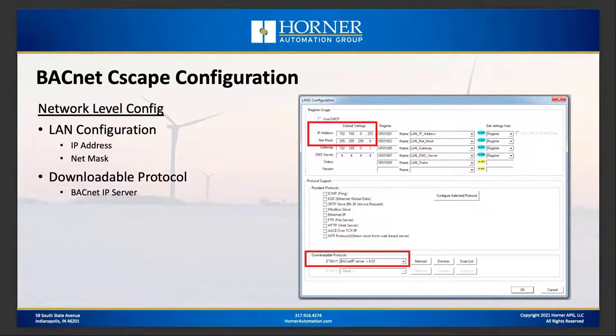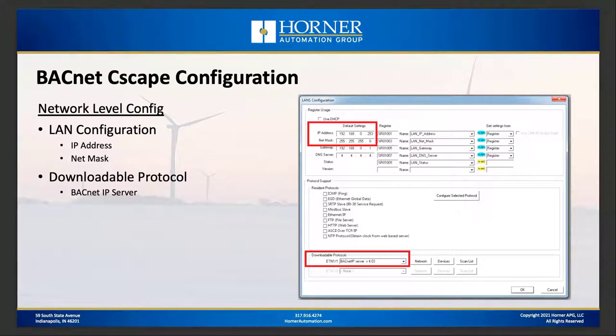For configuration in Cscape when configuring an OCS as a BACnet server, you start at the network level configuration. Go to hardware configuration, then under LAN 1 or LAN 2 for a two-LAN Horner OCS. At minimum, configure the IP address and net mask since BACnet IP is an Ethernet protocol. Then under downloadable protocols, select the BACnet IP server option. The very latest server option is version 4.05, and I'll cover what enhancements that version includes in a few minutes.